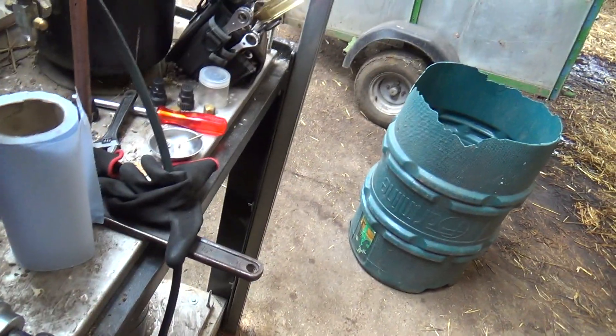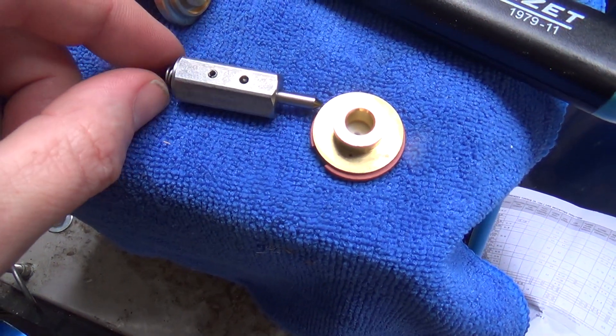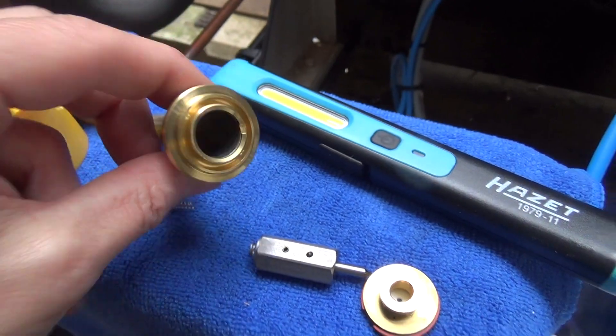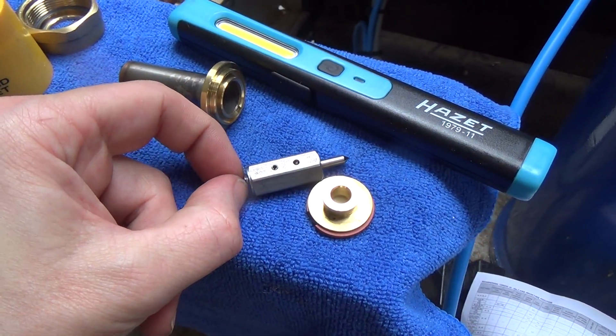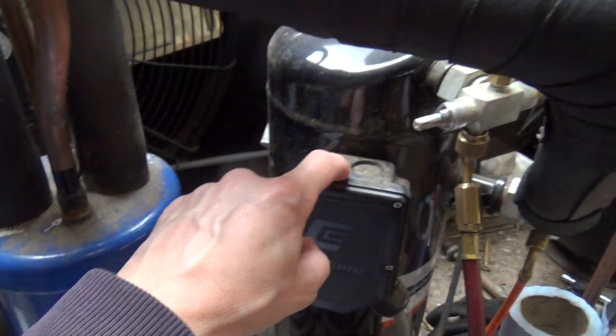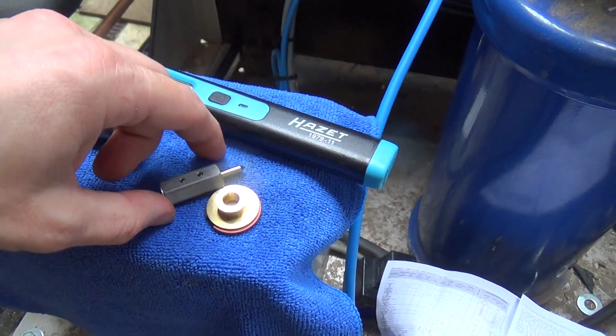Seen travel up the system. Found that spring. I've not found any rubbish in there - I was thinking I was going to find some, a bit of swarf in there or something, because that compressor was a bit noisy when we fired it up and I wondered whether something had worked its way through. But it seems pretty good.